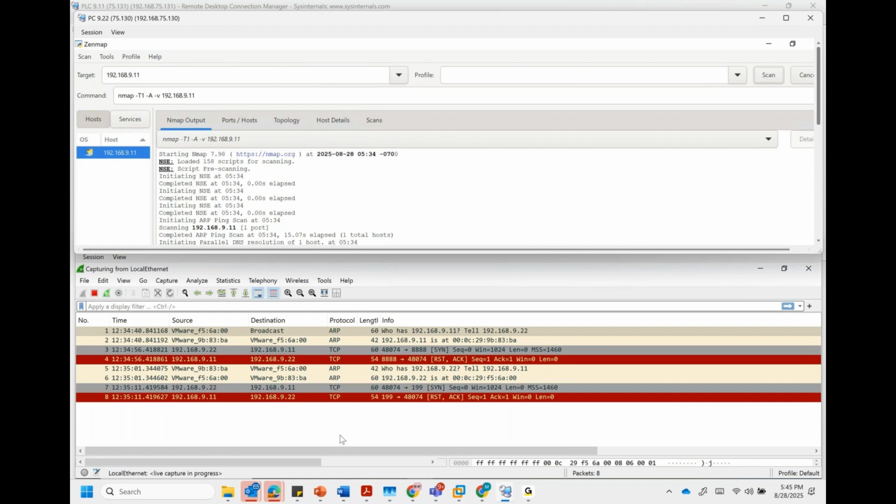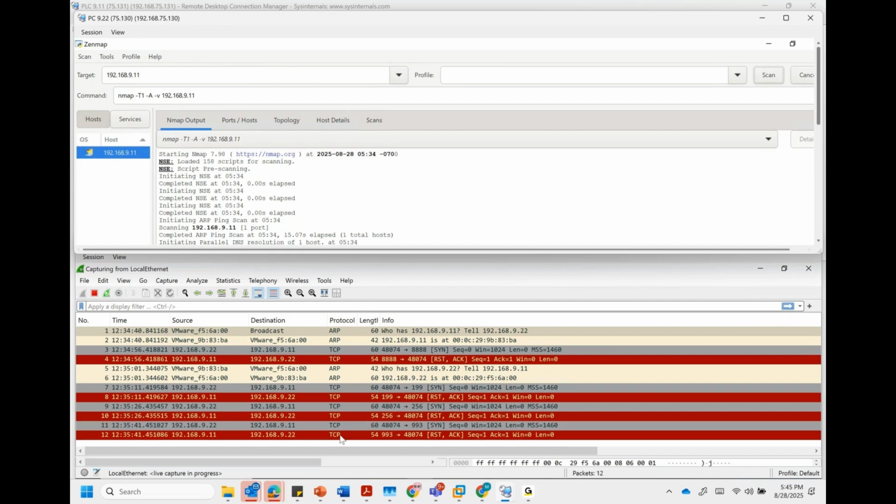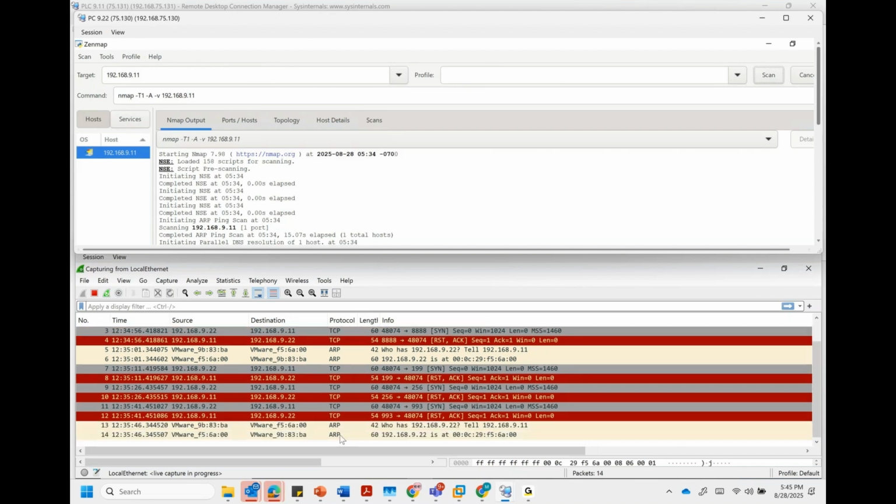So what we've done is that we are still using the same commands that are okay to run even with a legacy PLC, because if it supports the Ethernet protocol, it would be able to respond to those packets. It just cannot handle lots of packets at the same time. So if I slow down the communication and send one request at a time, every 5 seconds or 10 seconds, however much I want to slow it down, we have taken out that variable from the equation, that lots of packets, PLC doesn't like it. One packet at a time, one command at a time, the PLC would be okay with that.